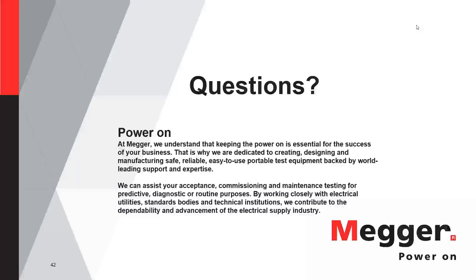On the other side, these methods, like Robert and Jason were saying, use limited energy compared to the substation, and you limit the amount of thumping or exposure to high voltage surges. It's not really damaging your cable to a point where you say, well, I'd rather not do that because I do more damage than I get benefit from it. No, that would not be a correct statement.